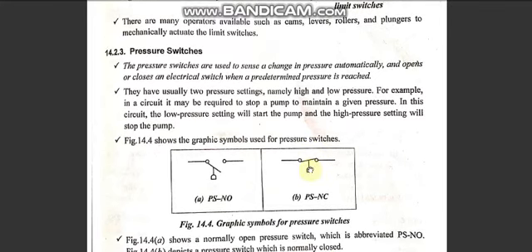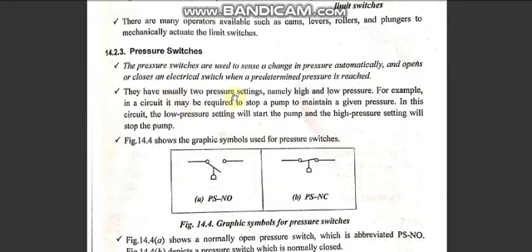Pressure switches are used to sense a change in pressure automatically. When the pressure exceeds or drops below a defined set point, the pressure switch automatically opens or closes. There are two types: normally open and normally closed. They usually have two pressure settings — high and low — and they are electrically coupled with solenoid valves to energize them.